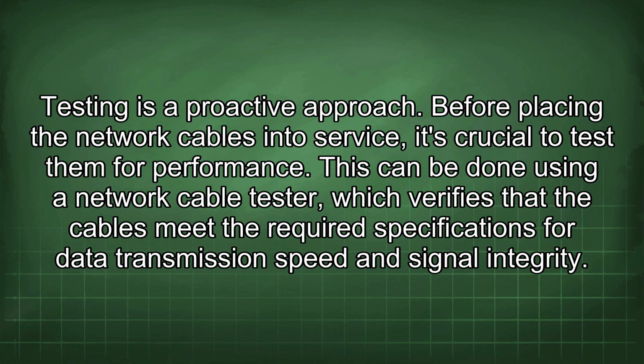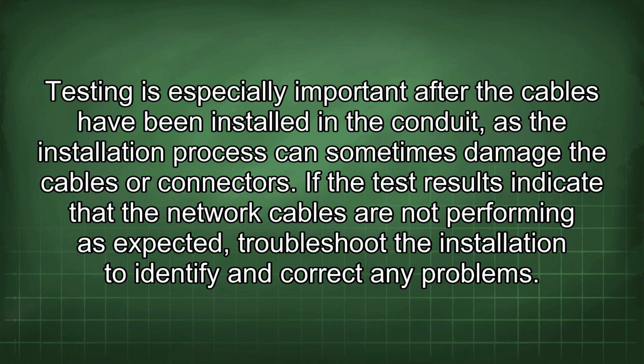This can be done using a network cable tester, which verifies that the cables meet the required specifications for data transmission speed and signal integrity. Testing is especially important after the cables have been installed in the conduit, as the installation process can sometimes damage the cables or connectors. If the test results indicate that the network cables are not performing as expected, troubleshoot the installation to identify and correct any problems.